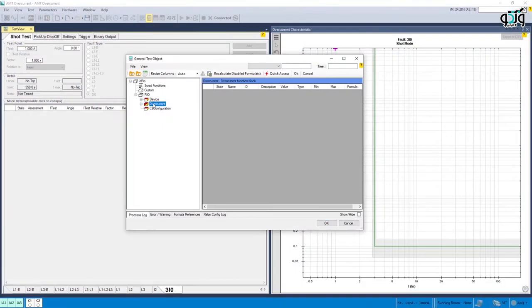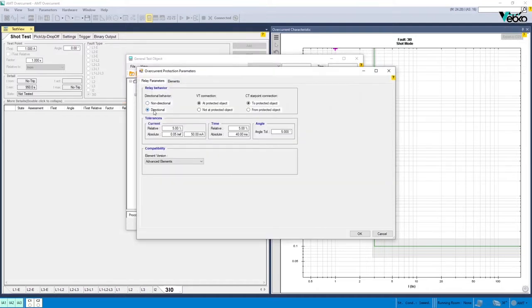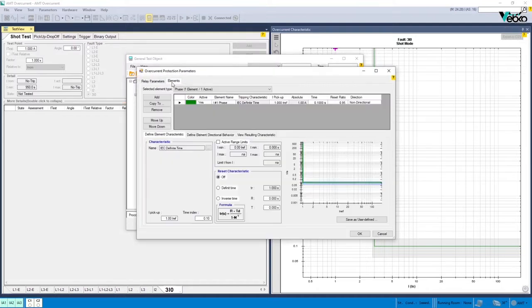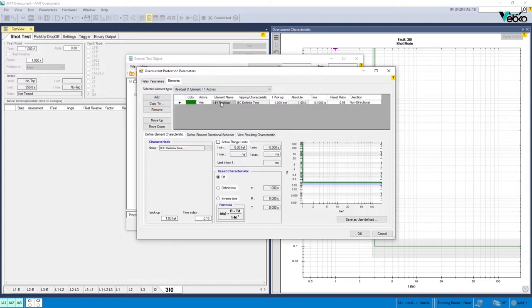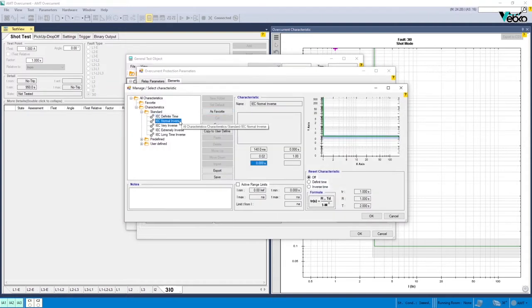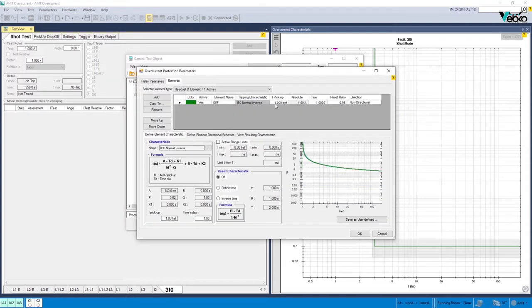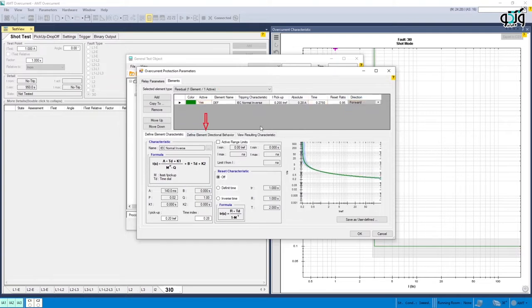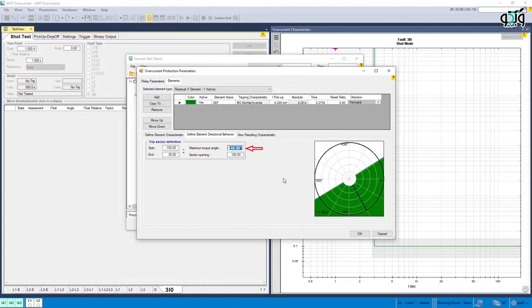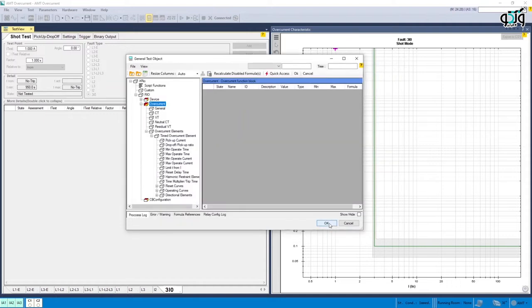If the user wishes to test the directional residual current function manually and without using Xtreo or CSV files, they only need to double-click on the overcurrent element in General Test Object window and by selecting the directional element in Relay Parameters tab, enter the setting values in Elements tab. Residual section is used for this purpose. Also, in Define Element Directional Behaviour section, the operation angle is entered. Here this angle is set at minus 60 degrees.